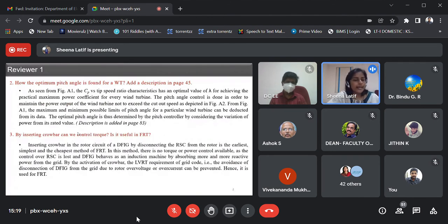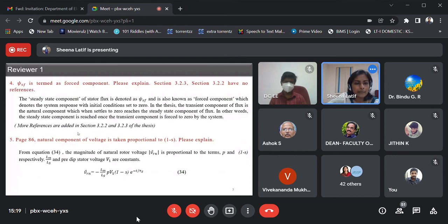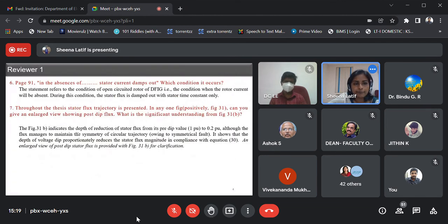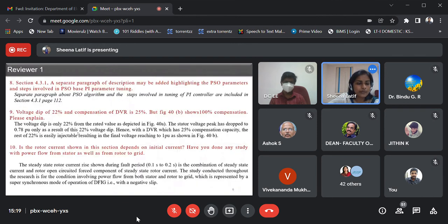By inserting a crowbar, can we control the torque? Is it useful in FRT? By inserting the crowbar, the control of the RSC is lost, and we cannot control the torque anymore. But being the cheapest method, it is practically implemented for FRT in many wind farms. Have you done any study with the power flow from stator as well as from rotor to grid? Our study is basically for the super synchronous mode of operation. So it has power flow from stator as well as rotor to the grid.